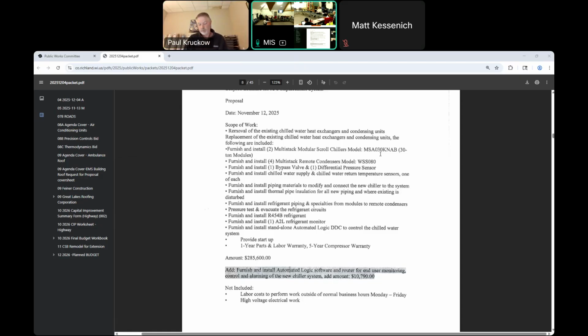I just wonder what KNAB stood for. Well, one of the things I can tell you is Multistack hasn't updated theirs. What's proposed here is the new A2L refrigerant, which everything is for 2026. There's nothing going out that's going to have R410A in it. So they have not updated there because there's still R410A stuff going out the door, and that's coming to a head real quick. Some of that R410A isn't available anymore, and this is still a brochure that they haven't updated yet on their website. It doesn't have the A2L refrigerant nomenclature in there. So that's why some of that is going to look a little bit different. Okay, thanks. Good. Anyone else?